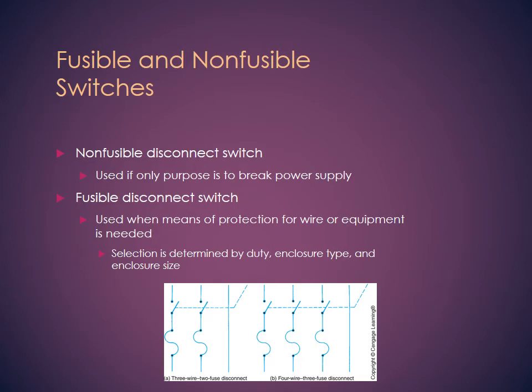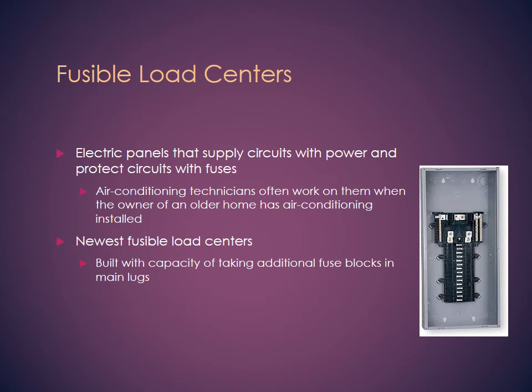Fusible or non-fusible, again, I showed you a picture of the fusible and non-fusible. It's basically a way to increase the safety for these control panels. This is a fusible center, and again, if you see, these are fuses between all the hot lines. We can use a fuse or a breaker. It's not the same. A breaker you can reset, a fuse you cannot reset. Some equipment is inductive, meaning it has a lot of induction, like motors or magnetism involved, and we might not want to use a fuse because the fuse will burn, and there's a possibility of a surge with that equipment. So check with the manufacturer and the equipment requirements whether you need a fuse or a circuit breaker.